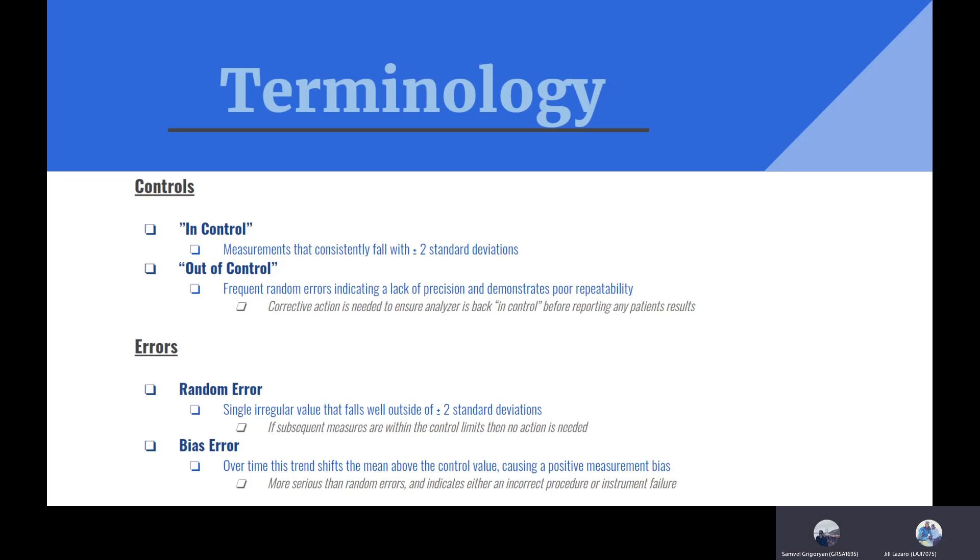When we go into calibration, we are looking at certain terminology that are specific for ABG analyzers. One of the first terms is control. There are two types of controls: in control and out of control. In control is what we want - measurements that are consistently falling within two standard deviations of our mean, staying within the lanes as it should.